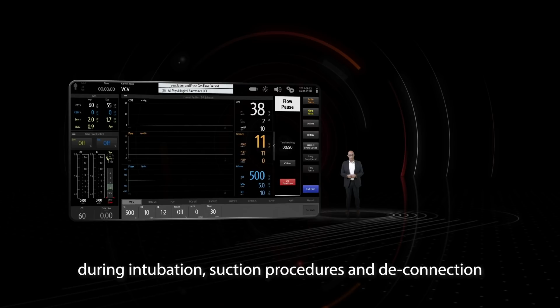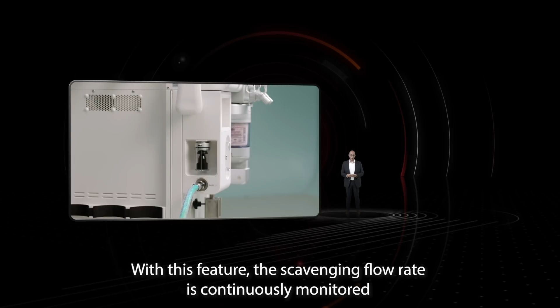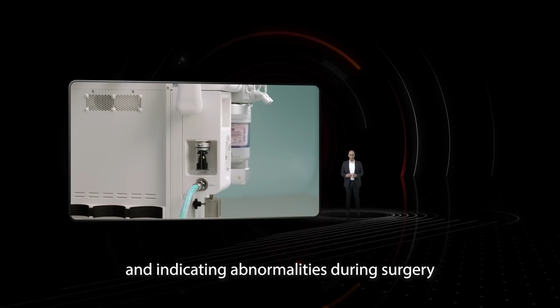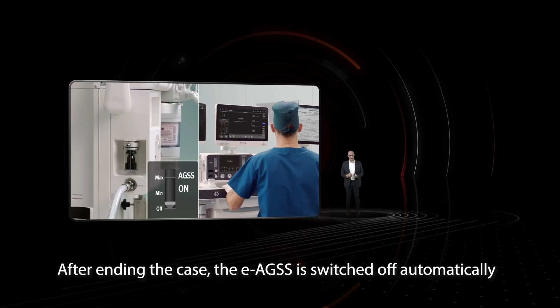This prevents unnecessary leaks of anesthetic gases into the operating room during intubation, suction procedures and disconnection for repositioning the patient. We have saved the best for last. The A9 has a completely new designed eAGSS, and that's the abbreviation for Electronic Anesthetic Gas Scavenging System. With this feature, the scavenging flow rate is continuously monitored and indicates abnormalities during surgery. After ending the case, the eAGSS is switched off automatically to reduce energy consumption.